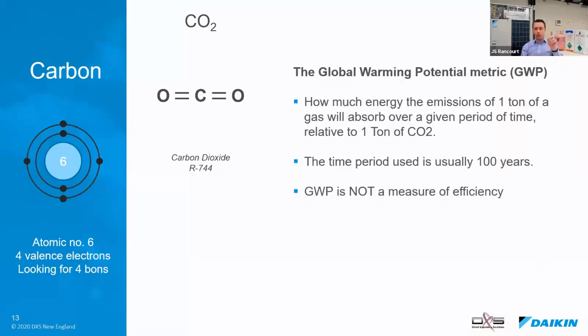This is where we introduce our first metric, which is the global warming potential of refrigerants. Essentially, how much energy will the emissions of 1 ton of a certain gas up in the atmosphere absorb over a certain period compared to 1 ton of CO2. So CO2 is our baseline. It gets a GWP of 1. Everything else is compared to CO2. GWP is not a measure of how efficient equipment is. It only looks at that molecule. If it gets up in the atmosphere, how much energy will it absorb compared to CO2?